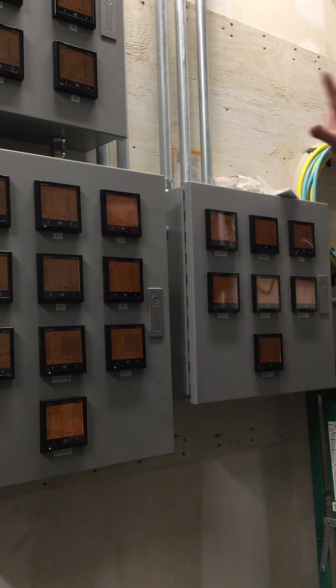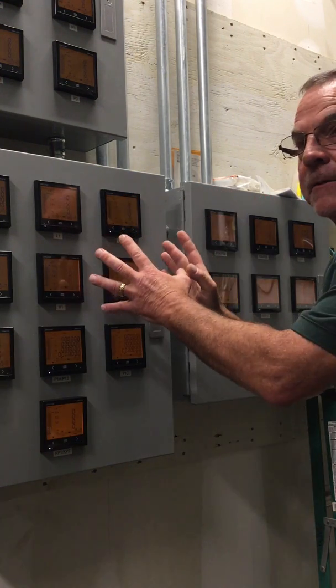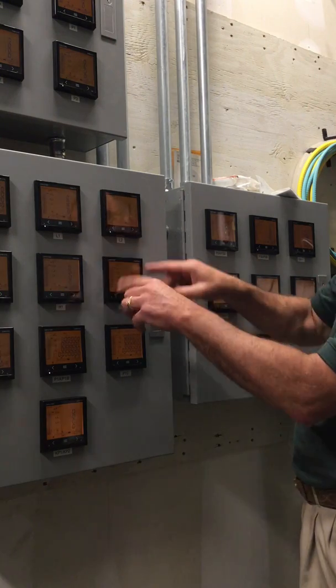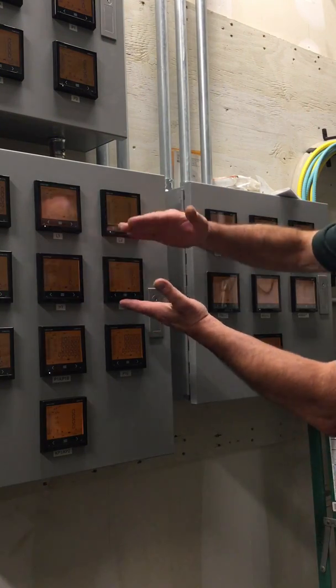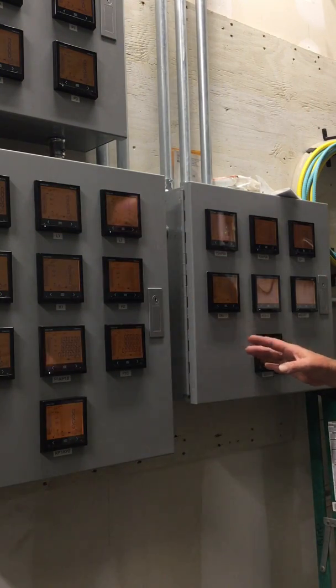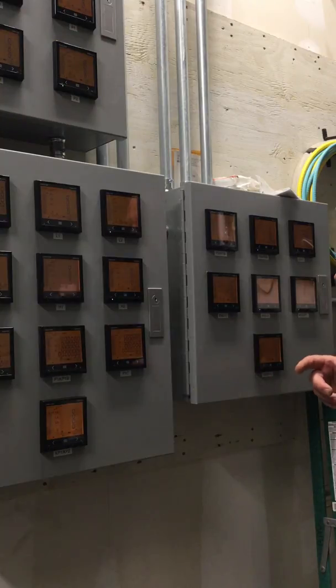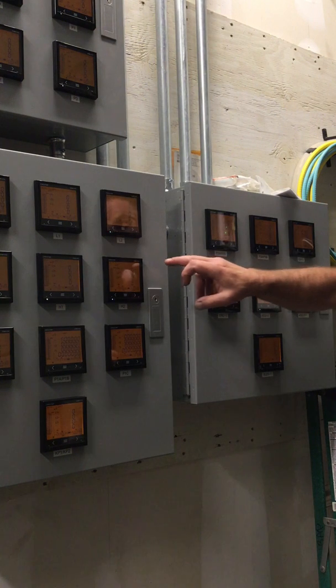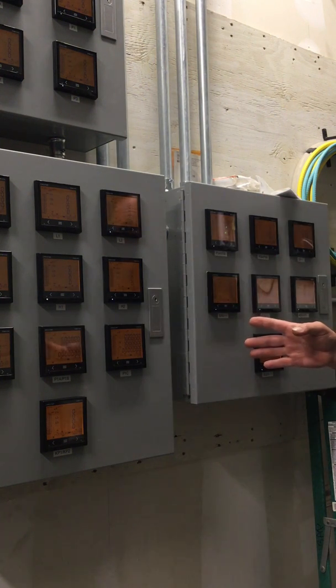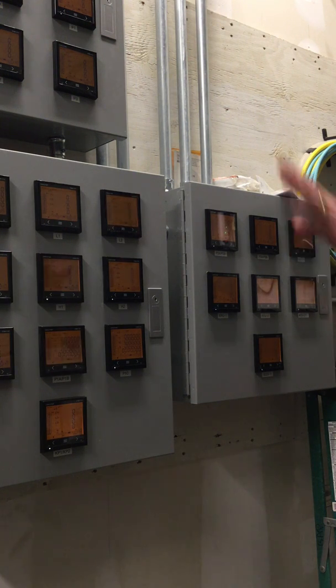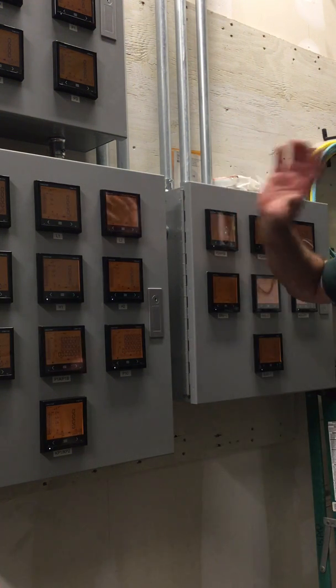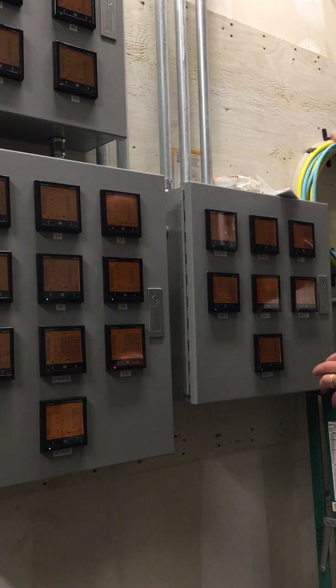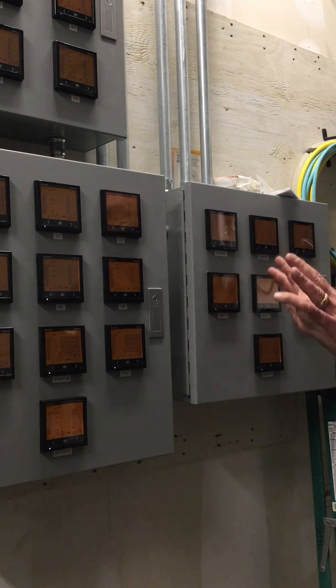If you come to any one of these and it's blank, not that the LCD screen, but the light's off, nothing's on it, that means it failed. It will shut itself off. So 99.9% of the time, nothing's ever 100% accurate, when the meter's up and running, it's within the accuracy standards. The meters came pre-programmed to the job site. At that point, electricians went and threw the current transformers onto the meters, hooked them up. At that point, good to go.